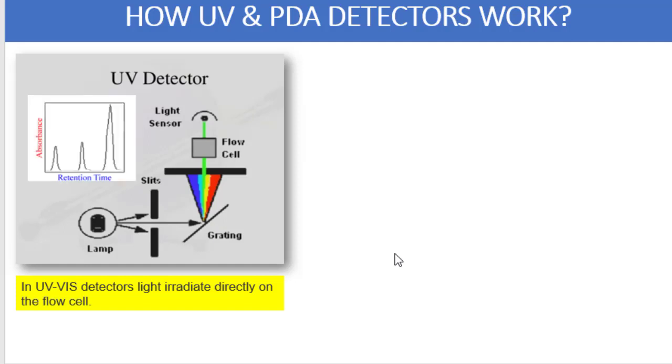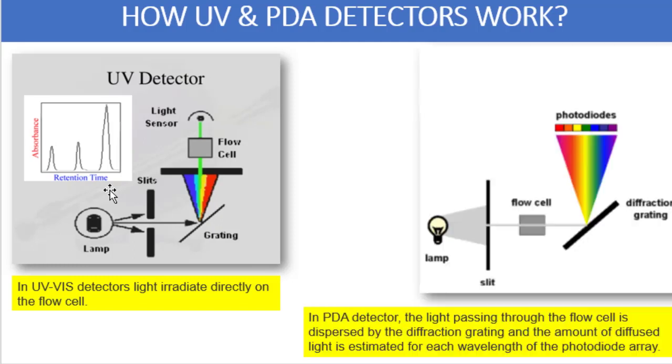We know that in HPLC the light absorbed is reflected as the signal. You can see on the chromatogram over here that there are three different peaks observed, and on the x-axis there is retention time and on the y-axis it is the absorbance. Let us now understand how the PDA detector works. If you look at the construction of the PDA detector it is a lamp followed by a slit, then immediately flow cell, followed by diffraction grating, and then there is a photodiode array on top of it.